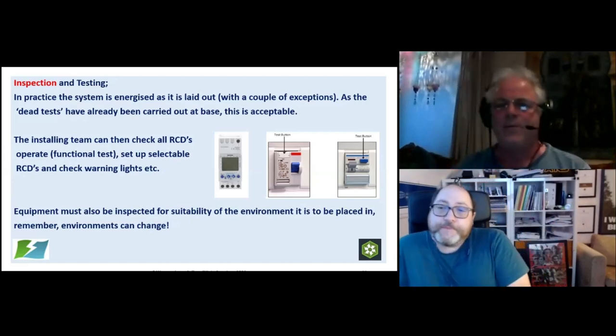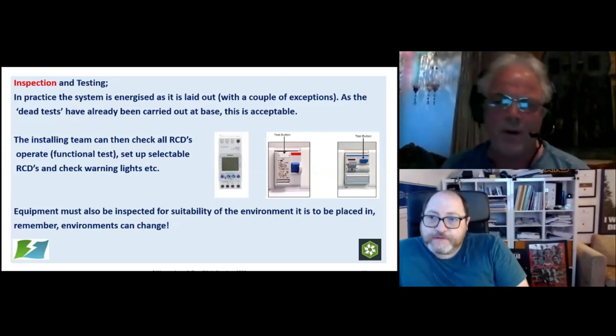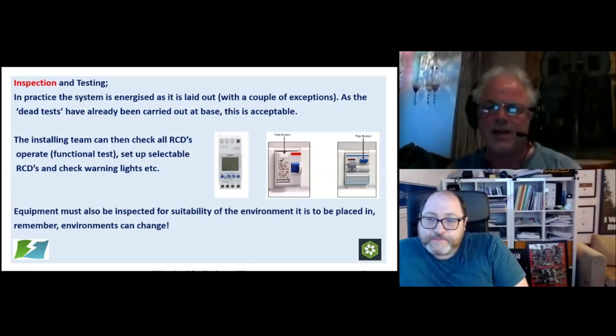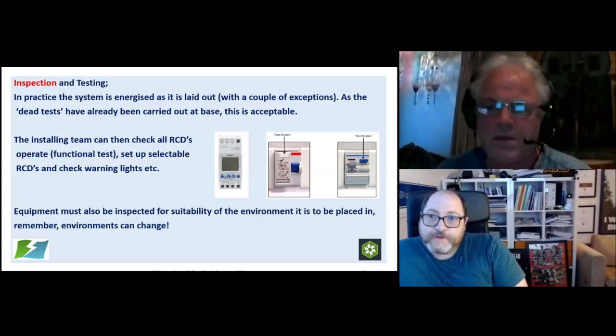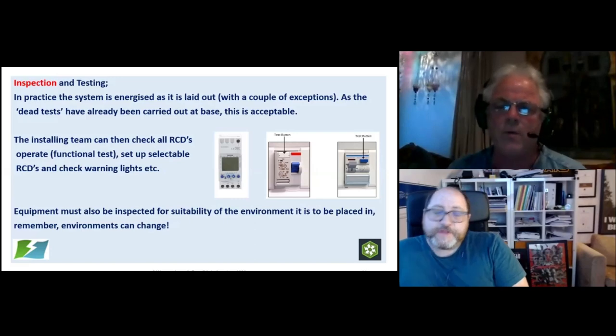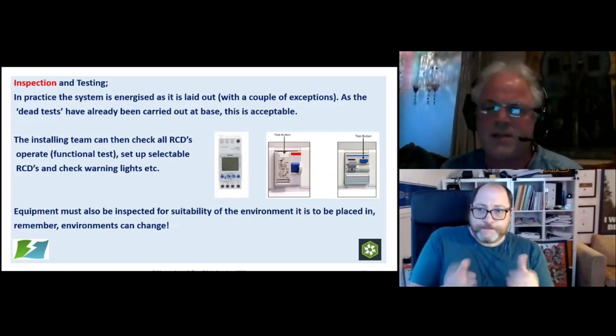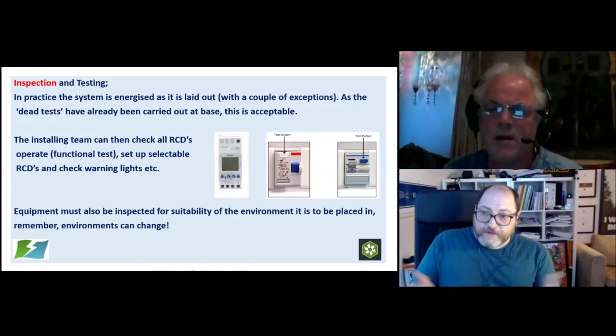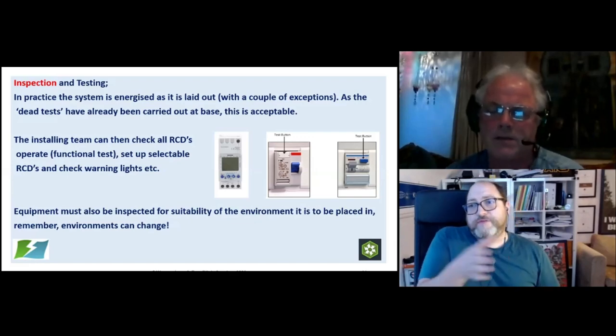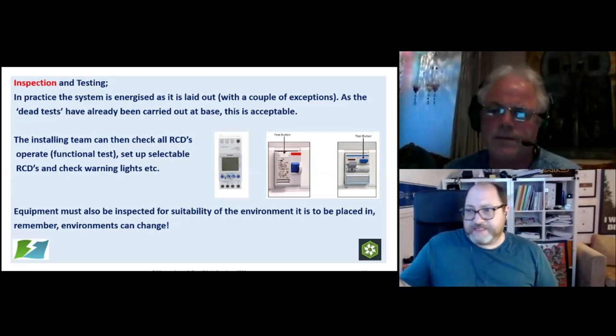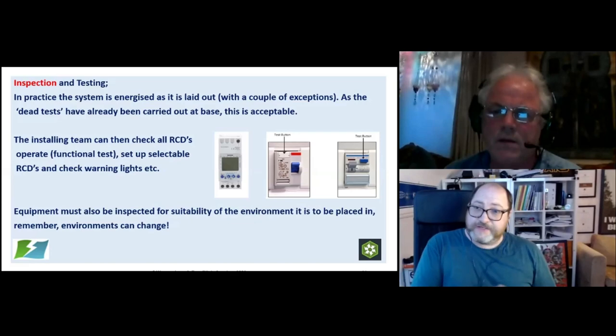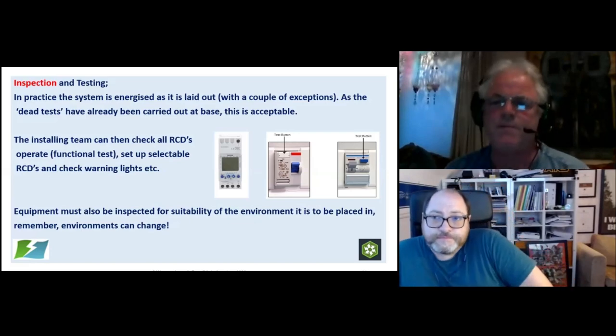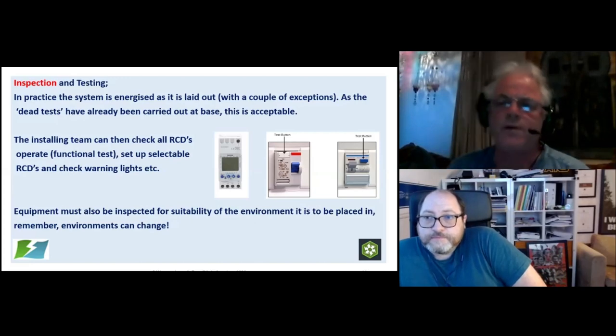I mean, people look at me a bit strange when I talk about a 1 amp RCD with a 1 second delay on it. Yeah, why not? It's a fairly common situation. When I'm doing major events, that's the sort of levels we're using. If you've got a large scale system and you try to put a time delay on the 30 milliamp, you'll have protective conductor current buildup, which will take that out straight away. No. 30 milliamps must be instantaneous, no time delay on all final circuits.